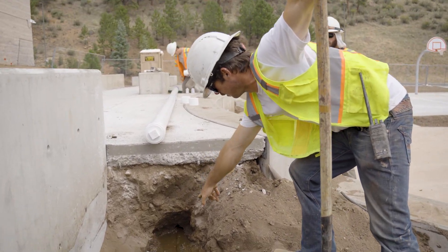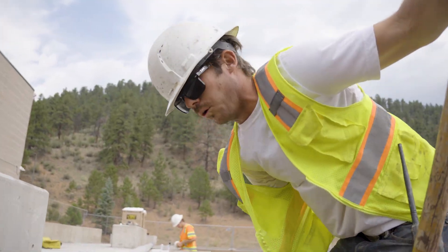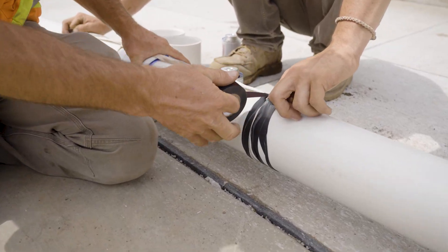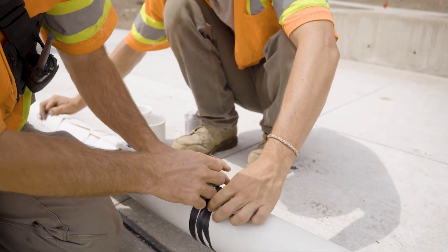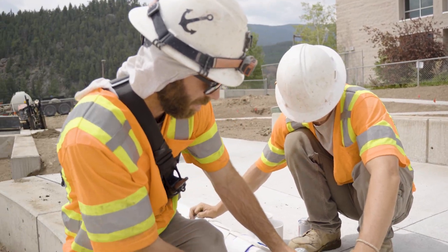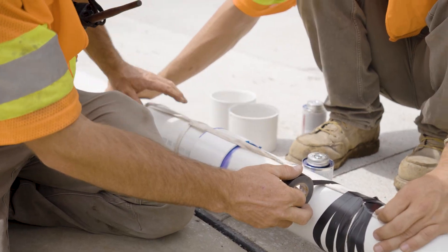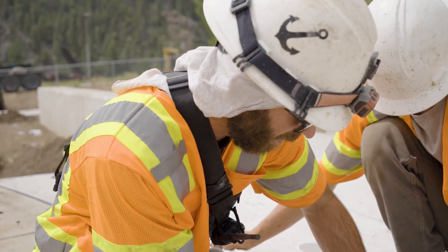So as soon as we get that reamer out to this hole, I'm going to have her push it all the way back out. The hole will be opened up and ready for the pipe — we'll hook the pipe on that side and drag it through. What we're doing is Chinese finger knotting this together so that when we pull it, it doesn't pull the seam apart. We glued this coupler and this yield tape is Chinese finger knotted on each side, and that'll help it stay together. We do not want it separating underneath.